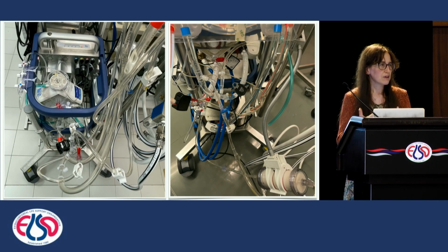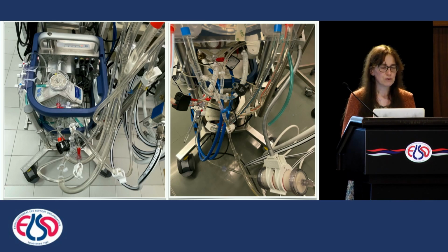Every connector is a potential source for thrombosis, a potential source for blood activation. Every connector could be the determinant of a circuit disruption and of the entrance of air within the circuit. So you need to consider carefully the pros and cons of adding anything to your basic circuit.